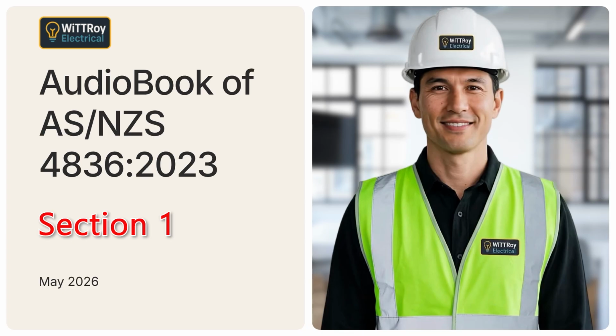Clause 1.1. Scope. Clause 1.1 explains what ASNZS 4836 is about. This standard provides safety principles, guidelines, and work procedures for people working on or near low voltage and extra low voltage electrical installations and equipment. The main hazards include arc blast, arc flash, electric shock, and electrocution. In simple terms, this standard helps workers understand what can go wrong, how serious the risk can be, and what controls should be used before starting work.